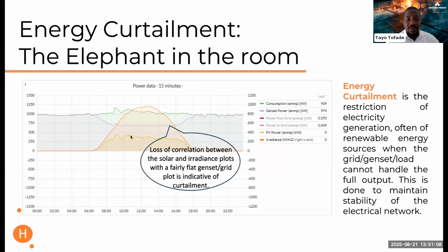So we see the solar line following the load perfectly, and the genset, the purple line, staying flat. The load is the green line, solar during the day follows the load, and the genset line is flat. The control system installed at this site has acknowledged the size of the genset, about 1.5 megawatts, with a base load of about 45%, meaning at every point in time there must be about 670 to 700 kilowatts on that genset for it to operate efficiently. That's what's causing curtailment at this site.